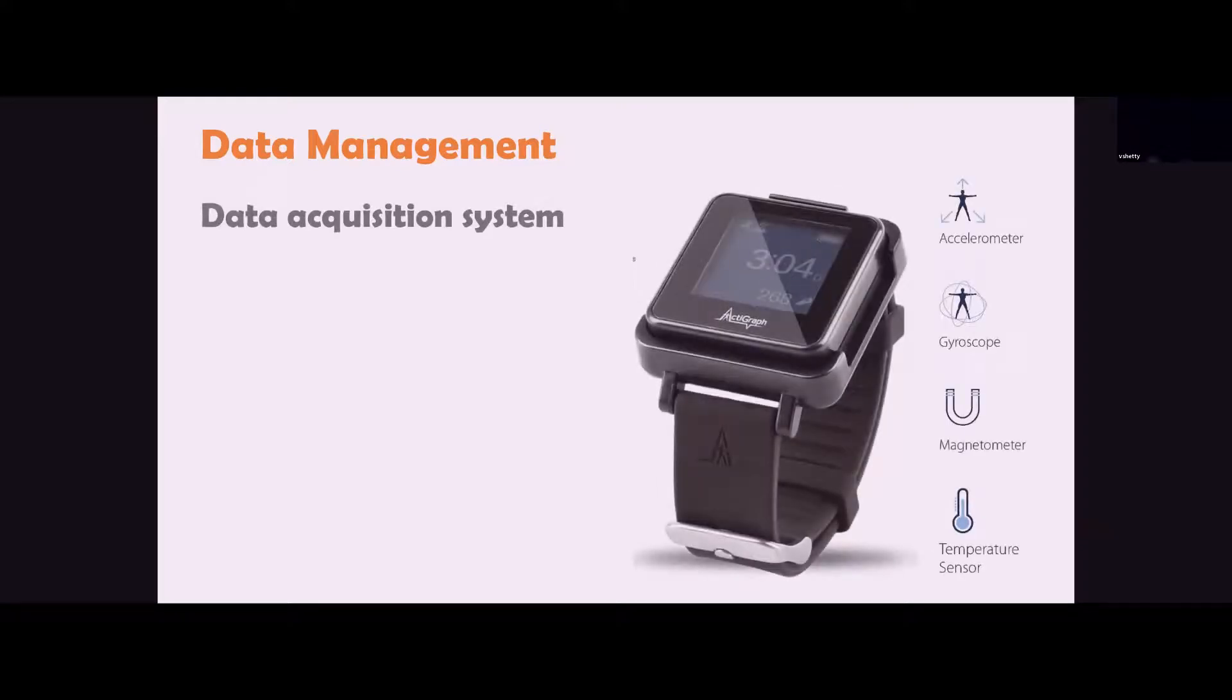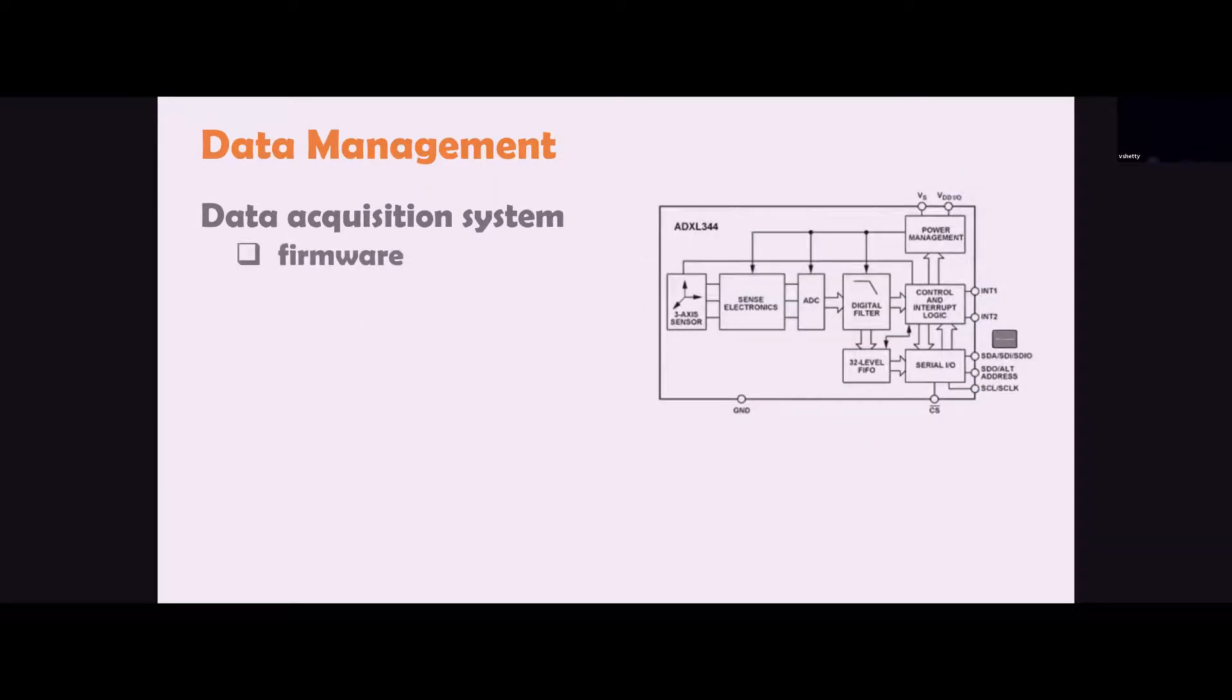Data management is another critical aspect you should be thinking about. For example, a common actigraph will embed things like an accelerometer, a gyroscope, a magnetometer, and a temperature sensor. Engineers usually use a combination of firmware and hardware and software to do the data management. Firmware usually controls basic device functions such as the configuration of data, logic programming, communications between and within hardware components using machine language commands. In a sensing module like this, you can quickly see it will have a sense electronics module to sense the motion captured by the three-axis accelerometer, and then it amplifies the signal and conditions it.